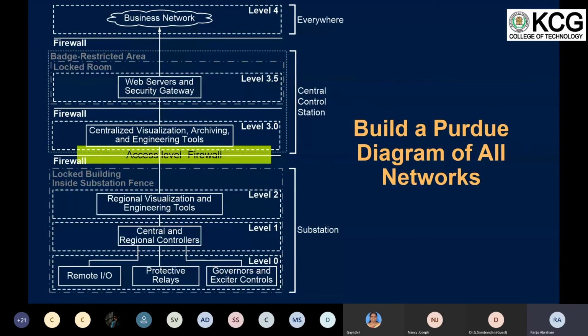This is the one I was talking about before: level 0, which has the protective relay and remote IED, level 1. These levels can also be segregated into substation levels - level 0, 1, 2, and 3 can be renamed in the architecture. The central control room, where the HMI, HMI PC, and other things reside, can be named as such, and everything else, the corporate network, can be given another name in the architecture.